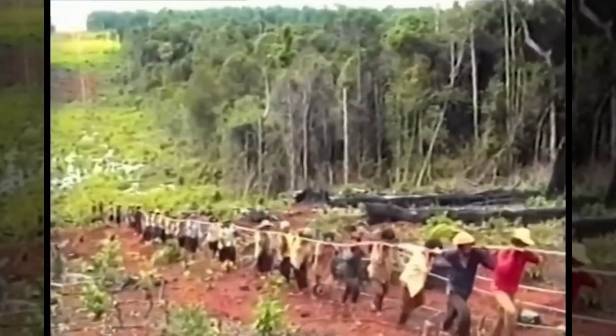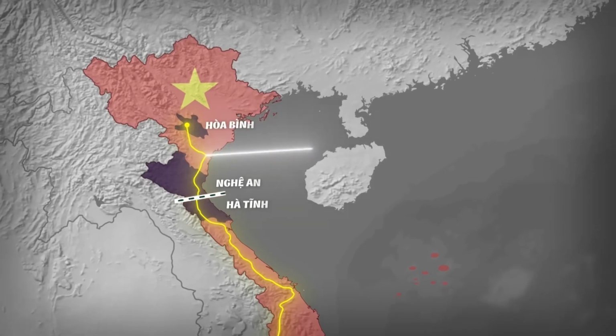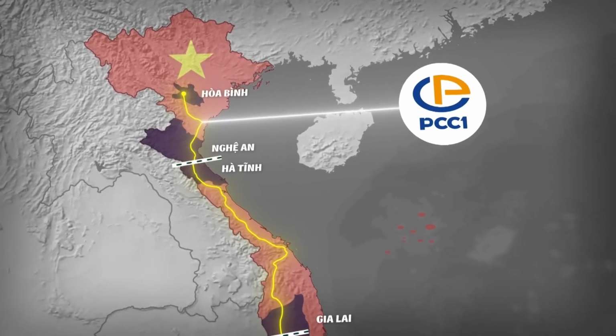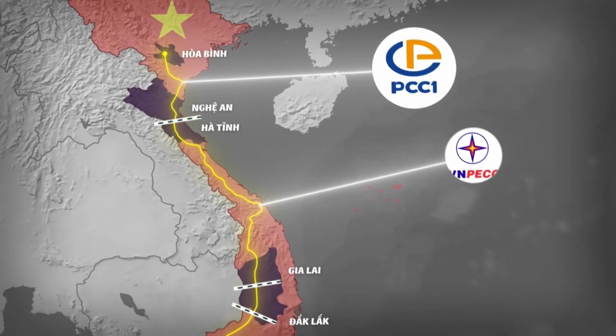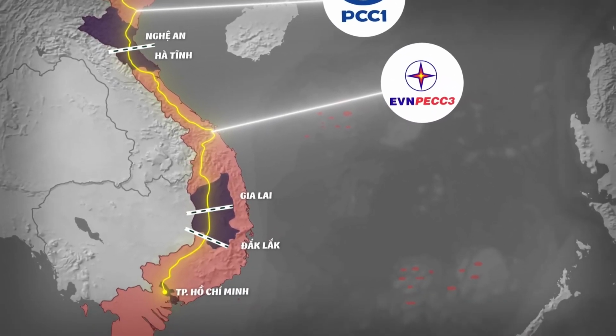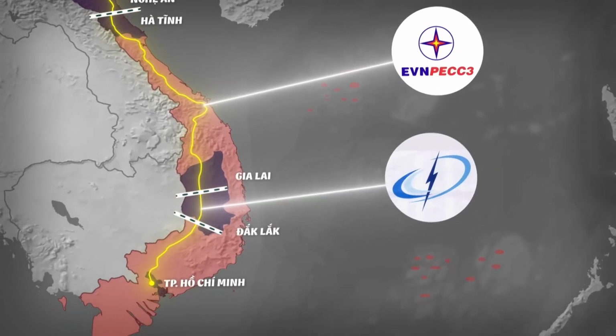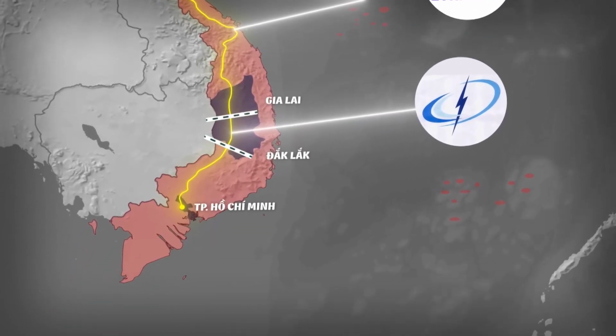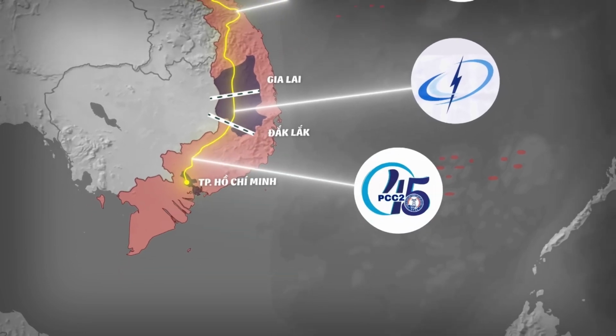This was considered extremely dangerous. According to the professor's explanation, electromagnetic waves have a sinusoidal shape, and 1/4 of a wavelength is exactly at the peak of the sinusoid. If the electromagnetic field in Hanoi reached its minimum level, it would reach its maximum level by the time it was transmitted to Saigon. Conversely, if the voltage was at its maximum in Hanoi, it could drop to 0 by the time it reached Saigon. In that case, it would no longer be 500 kV but could surge to 700 kV or 1,000 kV, causing all equipment to burn out.